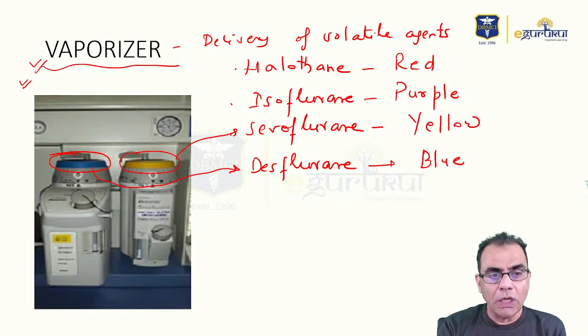No need to read all those labels. They write it also here, you can see it is written sevoflurane, but no need to read from a distance. We can tell that this is a sevoflurane vaporizer, this is a desflurane vaporizer. The halothane vaporizer will have a red code. Somewhere it is the knob color, somewhere the front part is of that color. Different companies have different designs, but somehow they will mention the color code on the vaporizer. So it is red for halothane, purple for isoflurane, yellow for sevoflurane, and blue for desflurane.